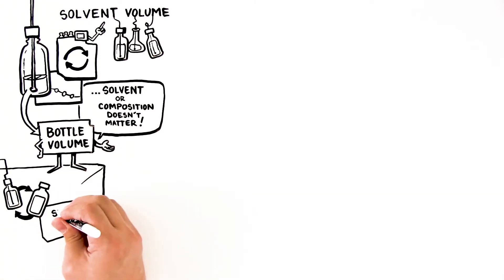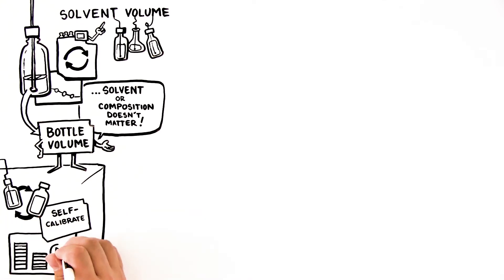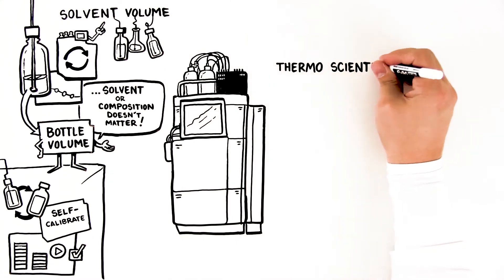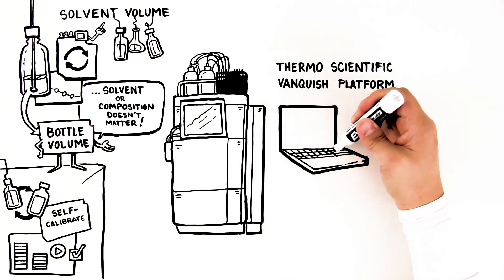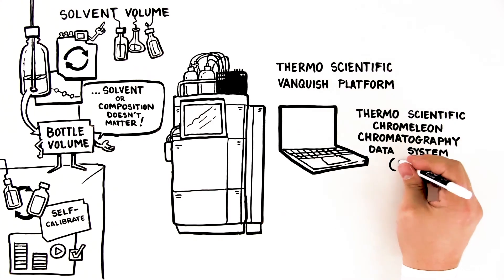Simply change the mobile phase, and the module will self-calibrate based on the solvent type and composition, and begin measuring immediately. This technology found in the VSM can be used in combination with the Thermo Scientific Vanquish platform. For the largest feature set, we also recommend using the device in combination with Thermo Scientific Chromeleon Chromatography Data System, CDS.